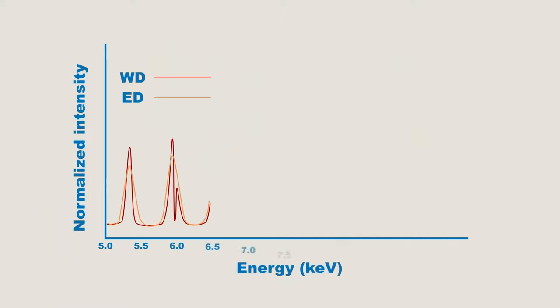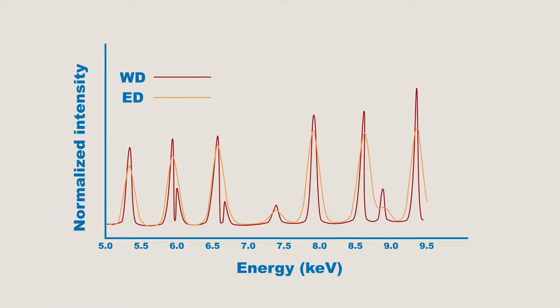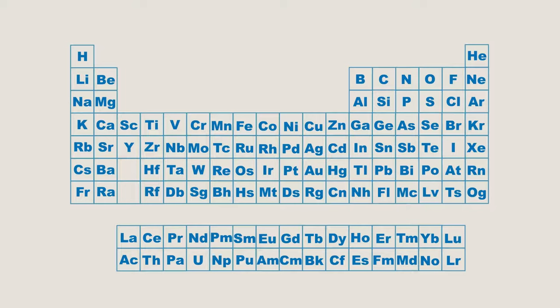WDXRF usually has better resolution than EDXRF, especially for the most common elements, which is mostly needed for advanced applications. Due to the higher power, WDXRF is also capable of measuring light elements that naturally have very low fluorescence yield and cannot be easily detected using EDXRF.